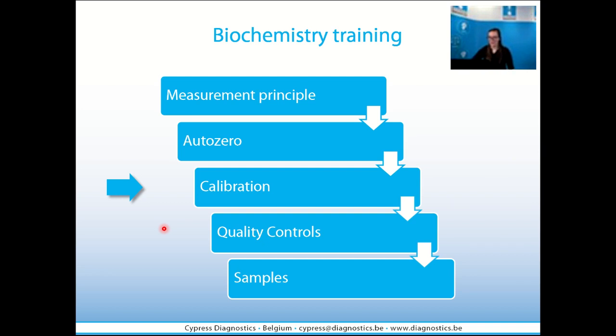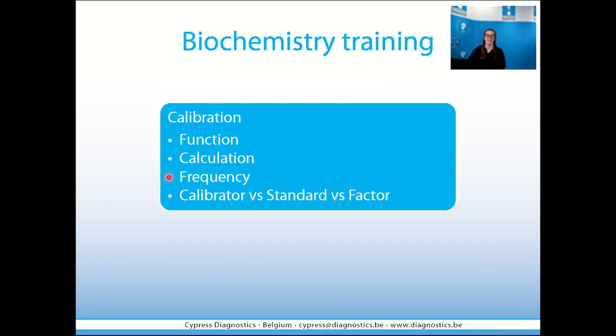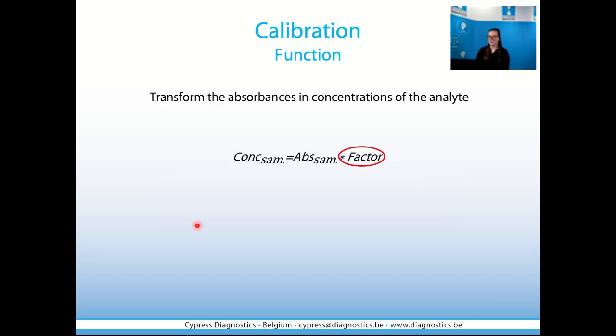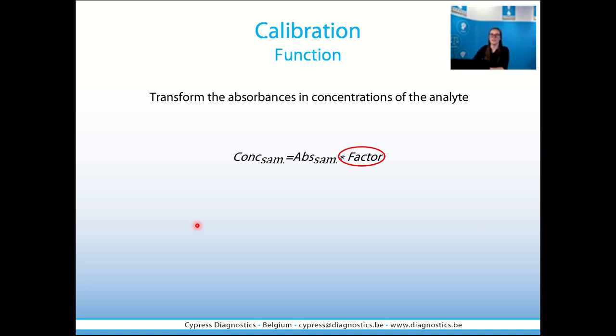What about the calibration? Why do we need to do a calibration? Because instruments only do one thing — measure the intensity of light. We cannot go to a doctor and say that for a certain patient, the detected light is higher than normal. The doctor needs concentration results. The calibration will transform the absorbance — the intensity of light — into concentrations of the analytes. We measure an absorbance, but we need the concentration. The relation between the two is the calibration factor.